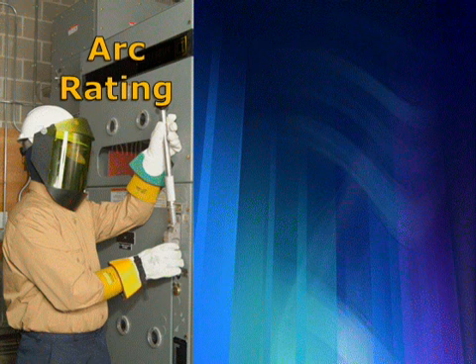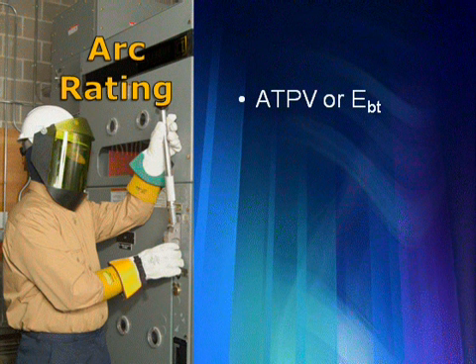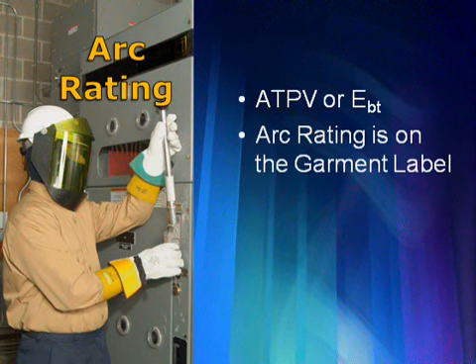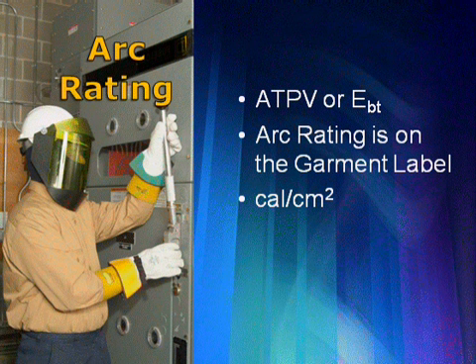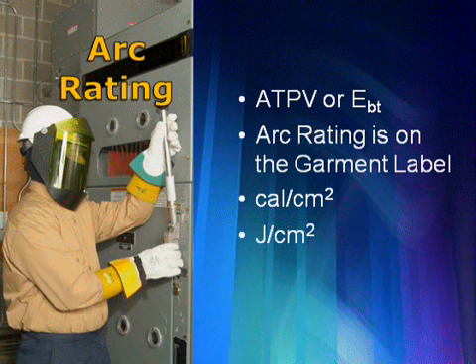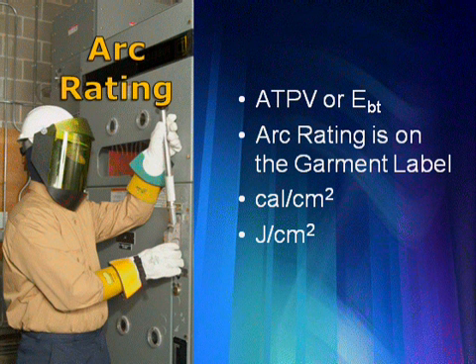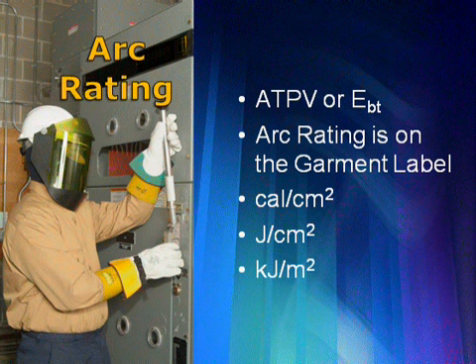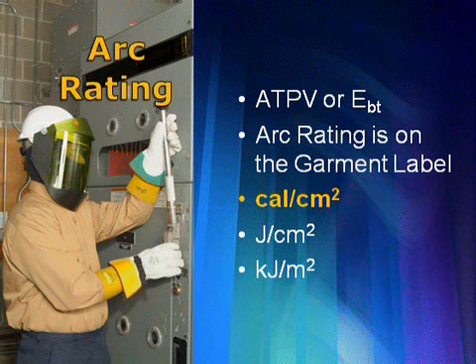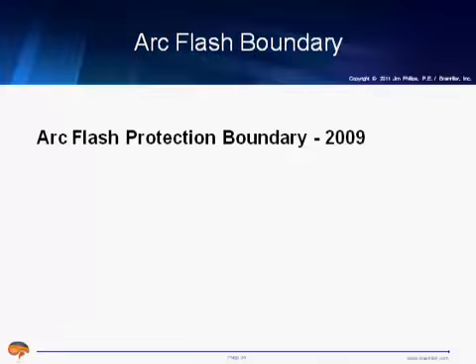And the arc rating, part of the incident energy analysis, is going to be the lesser of the ATPV rating or the break-open threshold. That's according to ASTM. The arc rating is required to be on the garment label. And for now, the way that we do this, arc ratings are based on calories per square centimeter. I do a lot of work with European standards and actually spend a lot of time in Europe, and they keep bringing up the fact that they would like to be metric, joules per square centimeter. Calories per square centimeter is, well, we'll call it half metric. And they've even discussed going to kilojoules per square meter, which is the true SI unit. But that would cause, I think, quite a few problems. So we're going to stick with calories per square centimeter.